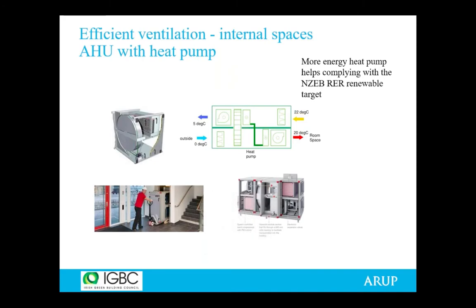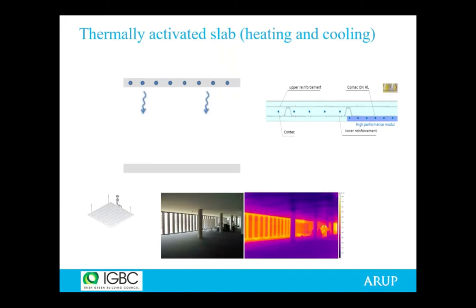So we're trying to do two things at the same time: complying with the renewables target and being efficient. So this system is, I think, one of the items that could be considered in your designs. Another low energy system, already mentioned, is heating or cooling the slab through embedded pipes running through. It's a slow response system, but it's efficient in the sense that it uses water not very cool or not very hot. And that's exactly what the heat pump wants.